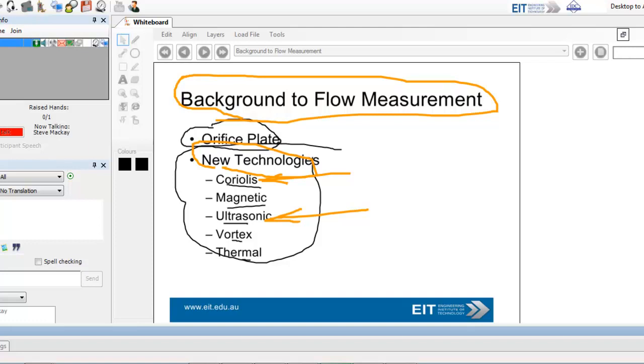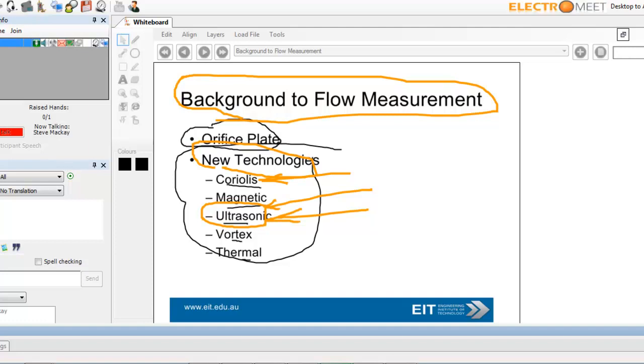What are the other ones? The other ones are ultrasonic, which is one of my favorites. I did a thesis on that many years ago. There was a lot of research. It was on cross-correlation flow measurement where you could actually profile the pipe, but it wasn't very reliable. So the typical flow meter ultrasonic technology they use today is called transit time, which basically you send an ultrasonic signal across the pipe at an angle, measure the time it takes for the signal to travel from one side to the other. And when your signal's traveling with the flow in the pipe, you go a little bit faster. So you look at how long it takes the signal to cross the pipe in one direction. And then you look at the time for it coming back, and you work out your flow rate from that difference between the times. It's proportional to the flow rate. It's quite simple.